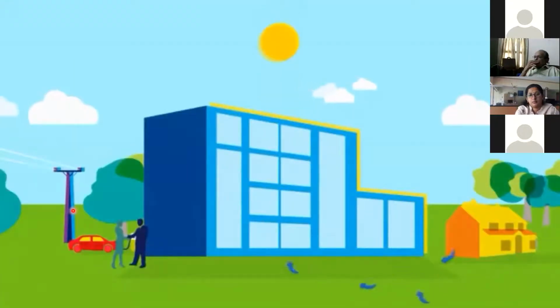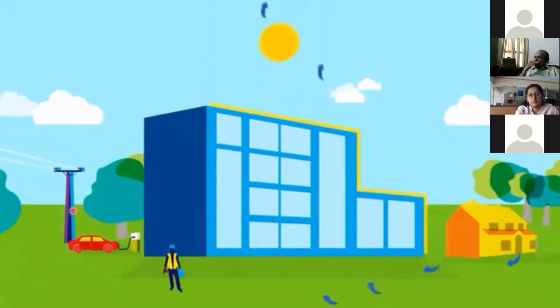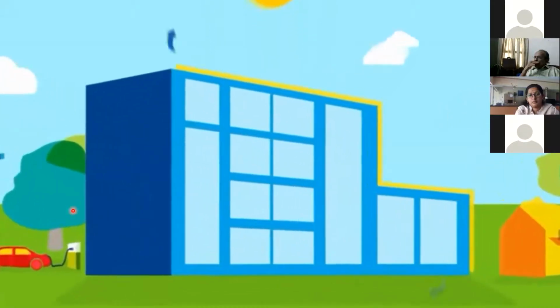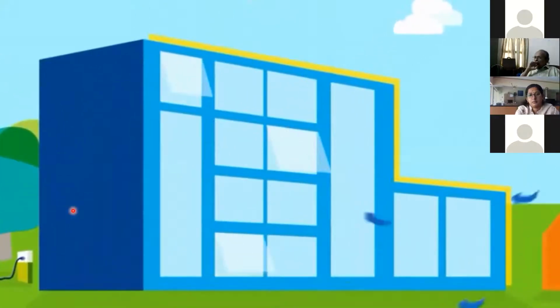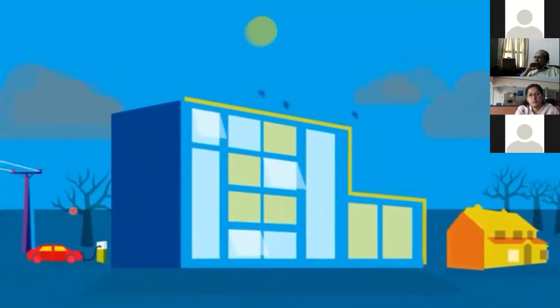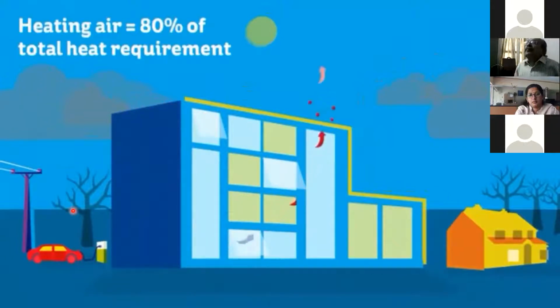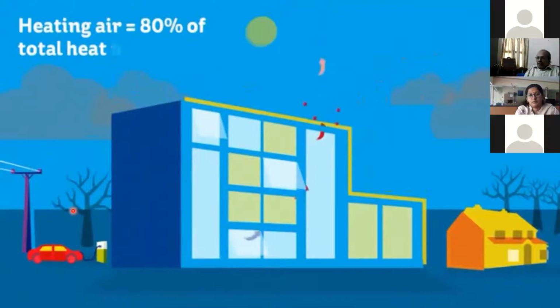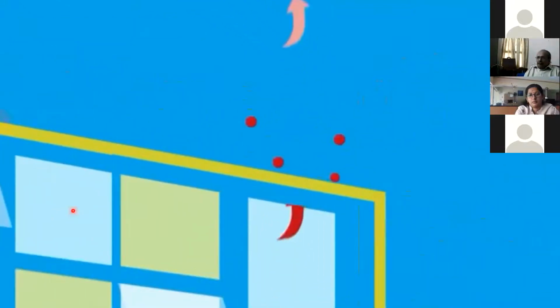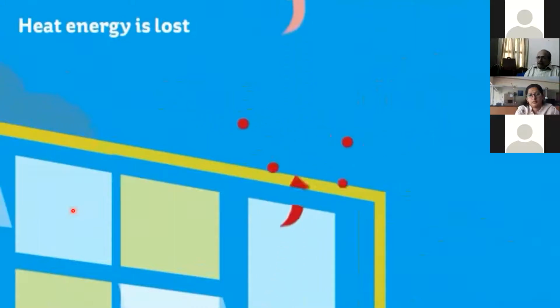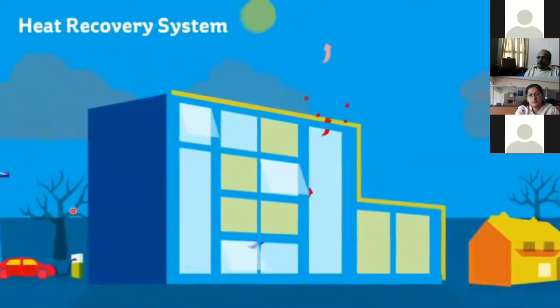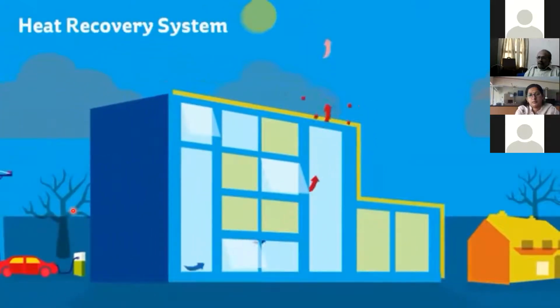In an office space, a large amount of fresh air is needed to maintain air quality. Traditionally, fresh air is provided by opening windows or by mechanical ventilation systems that blow fresh air into the building. During cold weather, this air has to be heated, which can account for up to 80% of the total building's heat requirement when an office is occupied. At the same time as the cold incoming air is heated, the warm exhaust air from the building is dumped. Heat recovery ventilation is a method of transferring energy or heat from waste air to the cold incoming air without compromising the quality of the fresh air.